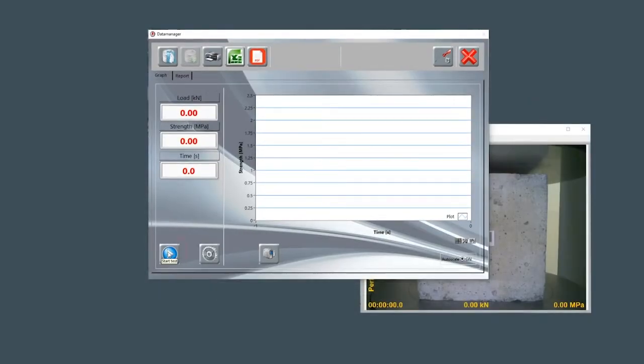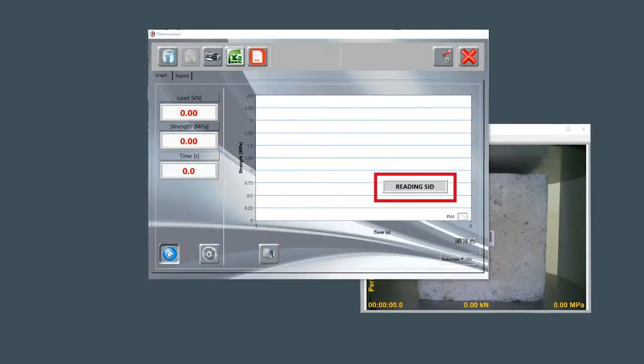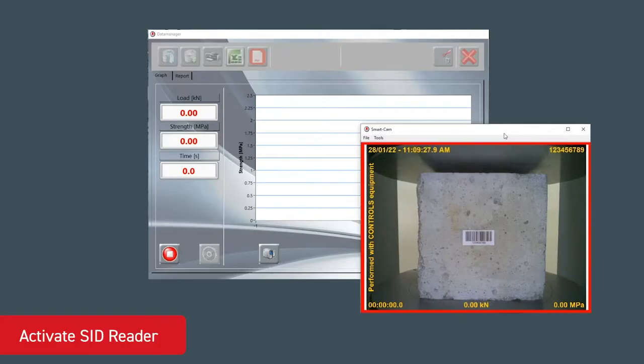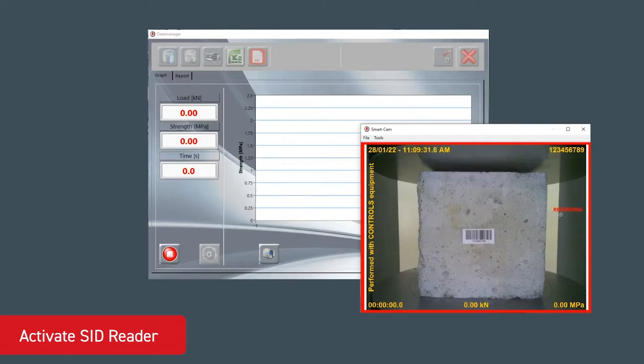Just after the test starts, a message reading SID appears, confirming the sample barcode verification. If the barcode on the sample matches the specimen ID, the test starts.